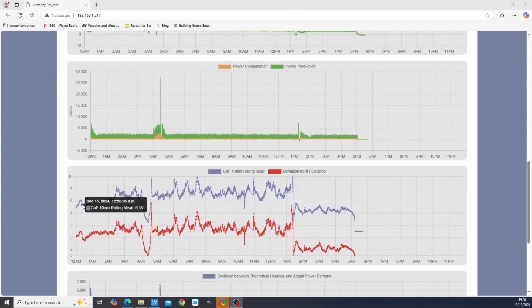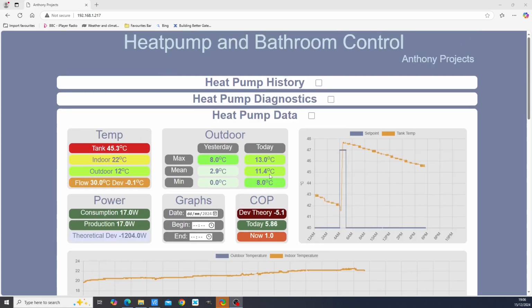You can see in the nighttime we had a coefficient of performance of about 6. This is stunning. And this is all just simply by stopping the temperature of the leaving water from dropping below 30 degrees for mild temperatures. During the middle of the day, we were getting up to 8 as a coefficient of performance. But look what happened here at 1:30. The heat pump stopped briefly and then it restarted. And then the coefficient of performance dropped down to about 4. So let's look in this regime here for a closer look. So if we go to here, 12 till 2.